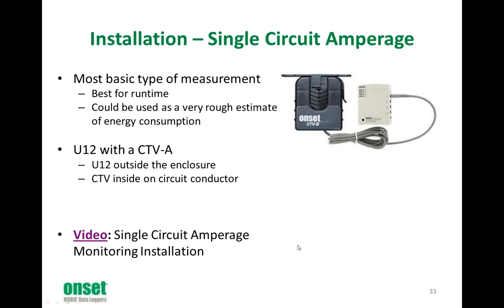Okay, and one other advantage of mounting the U12 to the outside of the electrical panel is you can do an interim site visit without the electrical safety gear and download the information off the data logger without opening up or accessing any of the energized conductors. So it's always a good idea to keep your logger outside of the panel whenever possible.